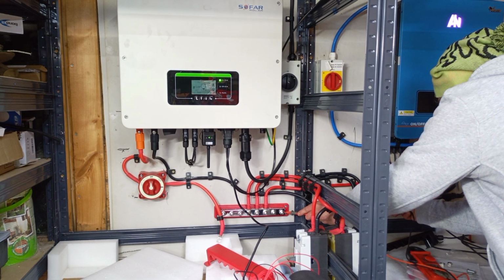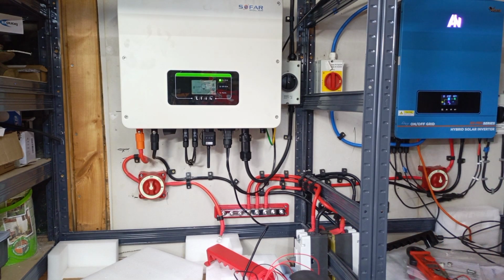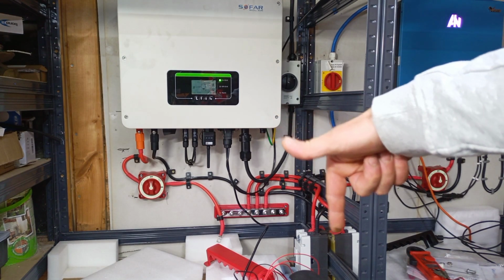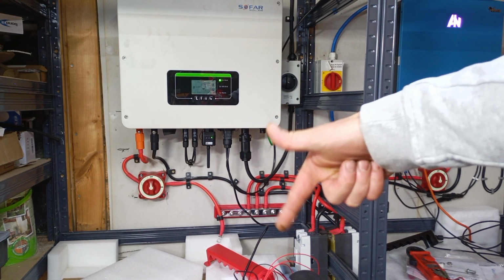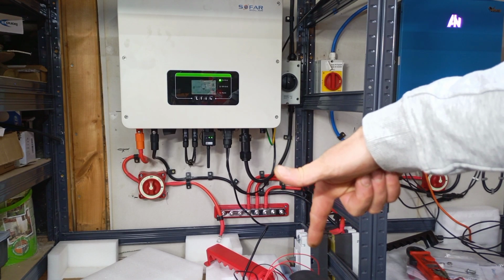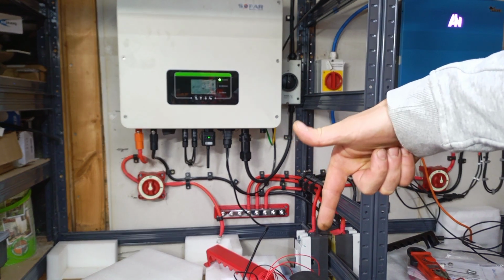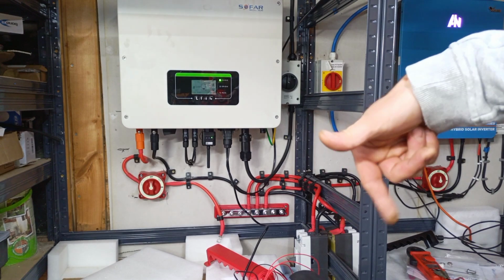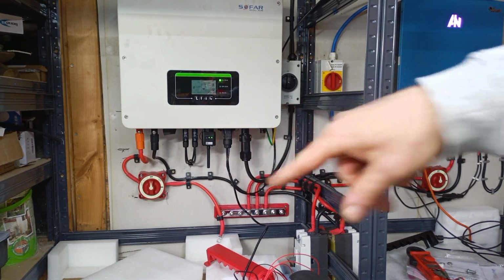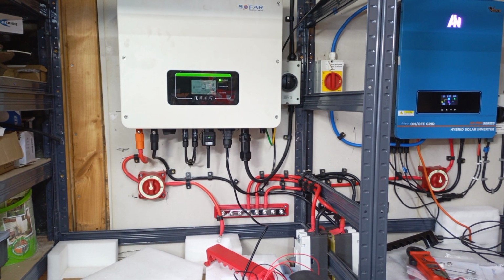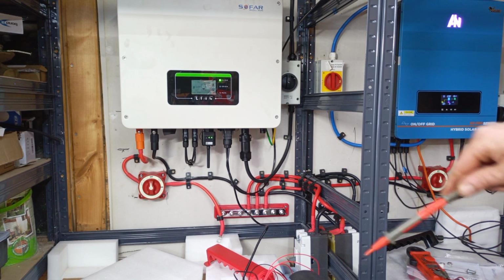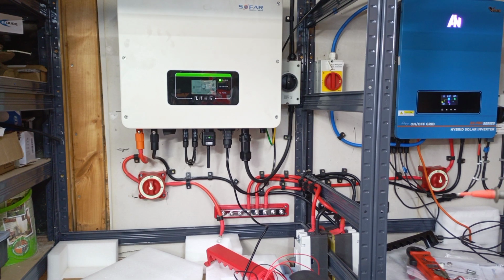And across the bus bars we are 0. There's something in the JK BMS, the new one. To start off with, it was showing 48 volts, but the pack voltage is 51.5. As I held the multimeter on the positive and negative terminals, the voltage ticked down and ticked down and got to sort of like 25 volts. So that's probably an internal capacitive discharge or something like that. But I'm happy we're all completely kaput-ish.